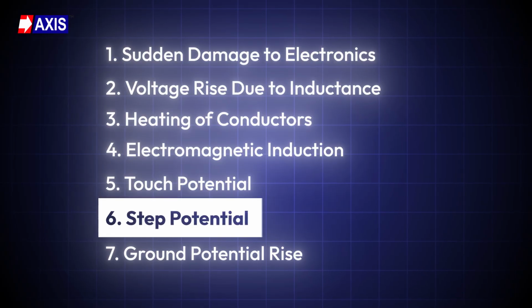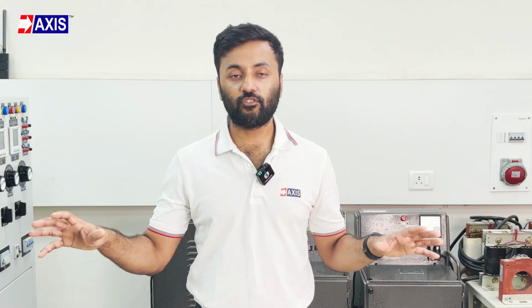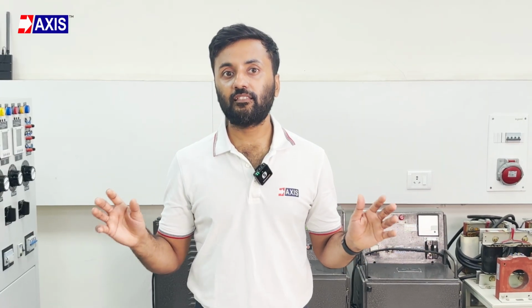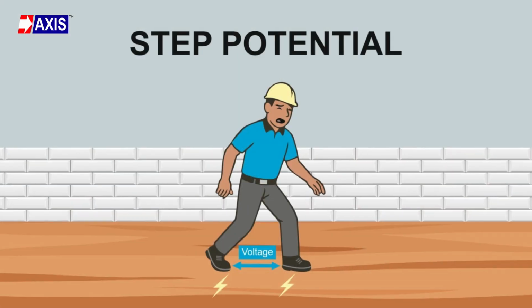Now, sixth, step potential. During a strike, a person or animal who's walking near the strike area might collapse, feel a shock, or show signs of muscle injury. This happens when lightning hits the ground and the voltage is spread out in all directions. The voltage is highest near the strike point and reduces with distance. If your feet are apart, each foot touches a different voltage gradient. That difference causes current to flow through your body.